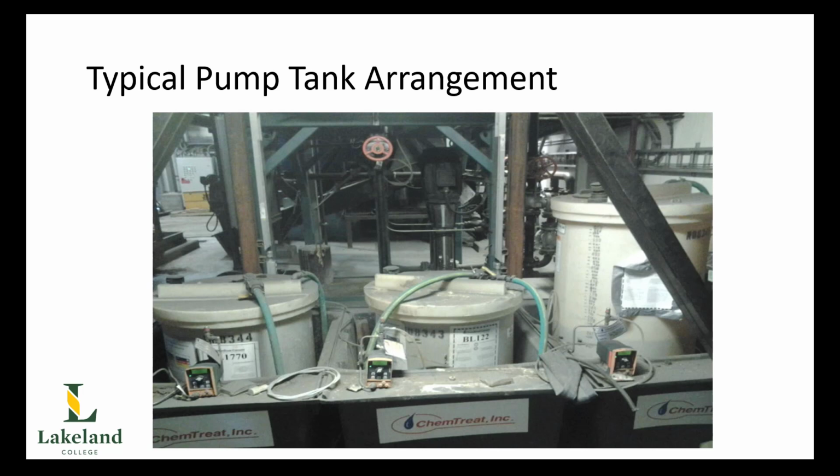You can see then there are the little chemical injection pumps in front of each tote, and that's what we'd adjust as the operator to adjust the injection rates to our boiler, to the deaerator, wherever abouts it's going. Of course, the chemical rep does need to come along at predetermined periods of time, and that's why you'll often see graduations marked on the side of the totes so that we know when to order more chemical.